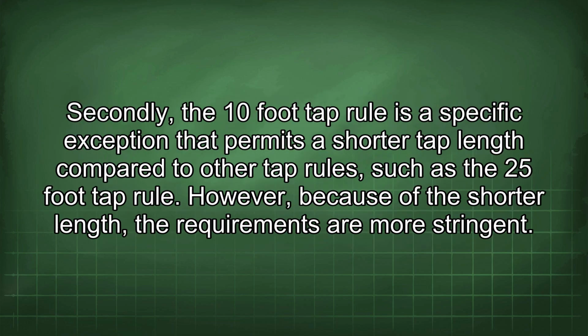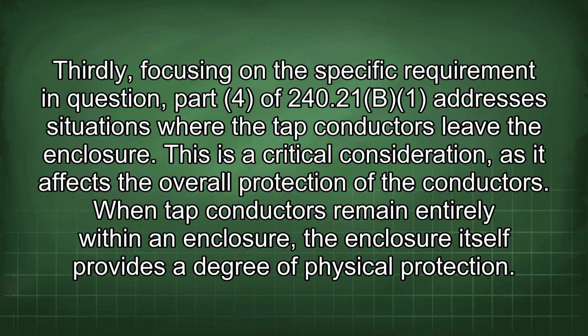Secondly, the 10-foot tap rule is a specific exception that permits a shorter tap length compared to other tap rules, such as the 25-foot tap rule. However, because of the shorter length, the requirements are more stringent. Thirdly, focusing on the specific requirement in question, Part 4 of 240.21(B)(1) addresses situations where the tap conductors leave the enclosure. This is a critical consideration as it affects the overall protection of the conductors.